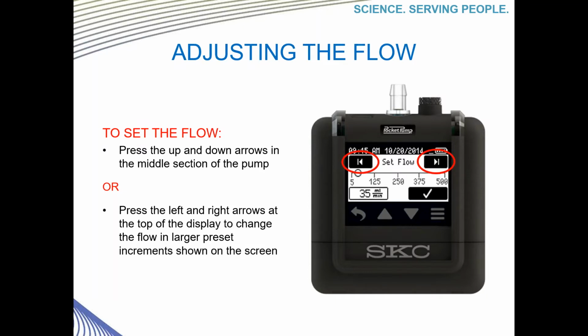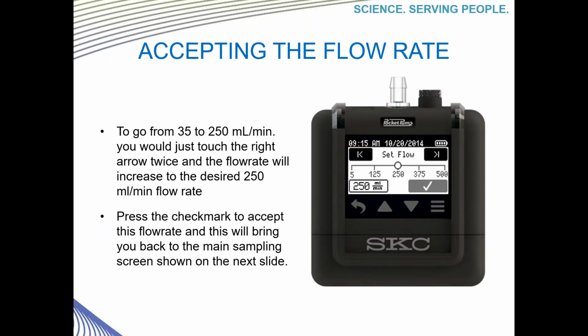You can make larger adjustments in flow rate using the left and right arrows to go to either 5, 125, 250, 375, or 500 milliliters per minute. And then you can use the up and down arrows to fine-tune the flow rate if it is not one of the 5 preset values. So now, to get our desired flow rate of 250 milliliters per minute from the current 35 milliliters per minute that the pump is currently set to, you would just touch the right arrow twice. Once you have reached the desired flow rate, you would accept it by touching the check mark on the screen. The flow rate has now been saved, and the pump will return to the main sampling screen.